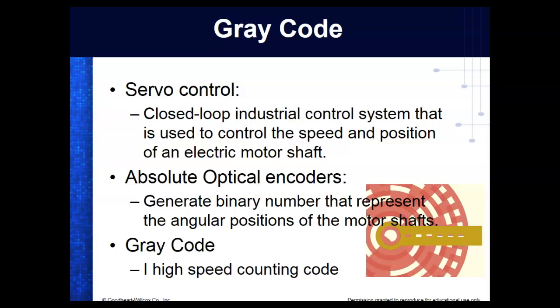So a digital counting circuit would always be faster than Gray Code that represents a counter. It takes quite a bit of actual machine language to cause a PLC to count. So PLC counters are relatively slow, and they can't keep up with these encoders that we use to represent speed and position on some of these robots. There is no way in the world a PLC counter, a software counter, can keep up with a hardware counter.